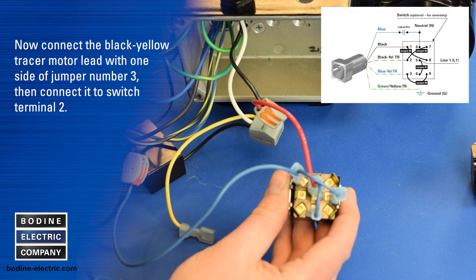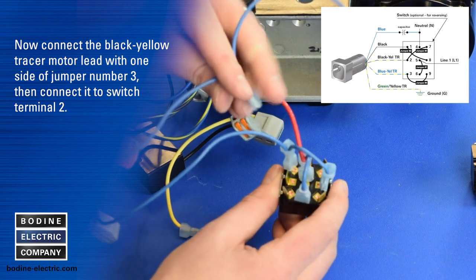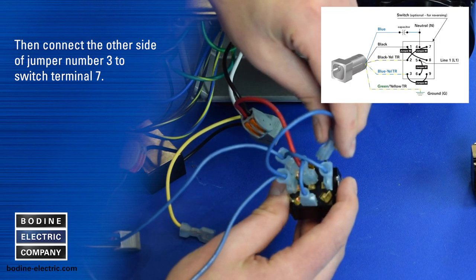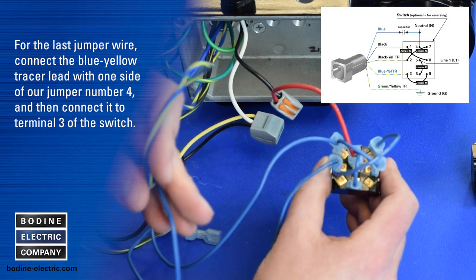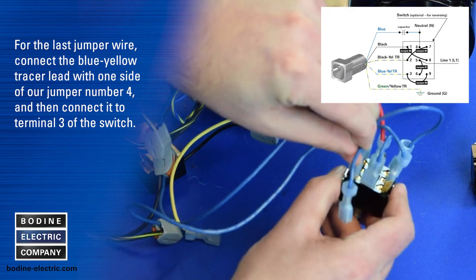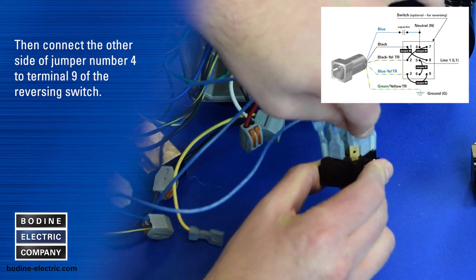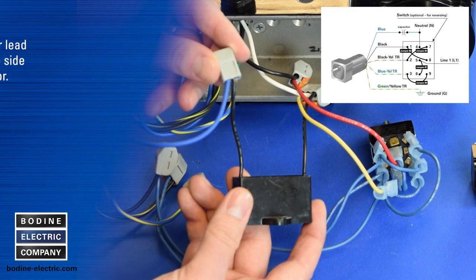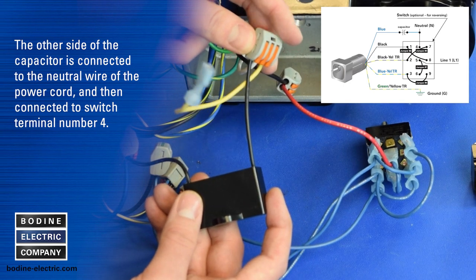Now connect the black-yellow tracer motor lead with one side of jumper number three of the switch. For the last jumper wire, connect the blue-yellow tracer lead with one side of jumper number four and then connect it to terminal 3 of the switch. The blue motor lead is wired to one side of the capacitor. The other side of the capacitor is connected to the neutral wire of the power cord and then connected to switch terminal number four.